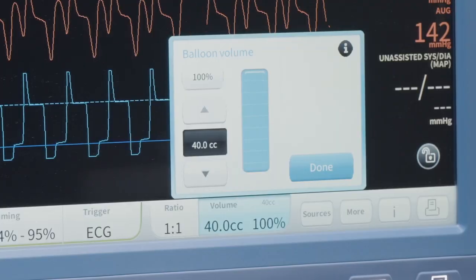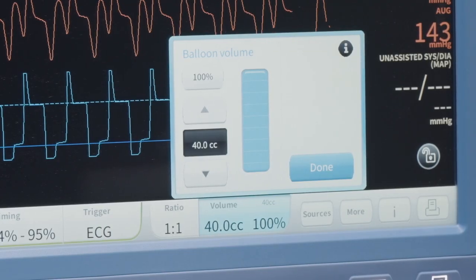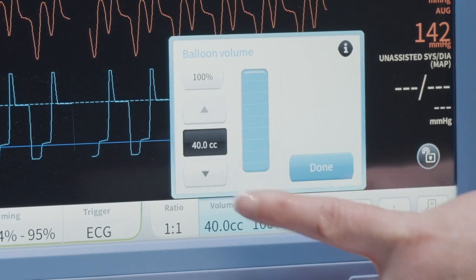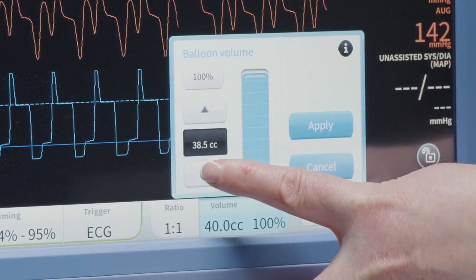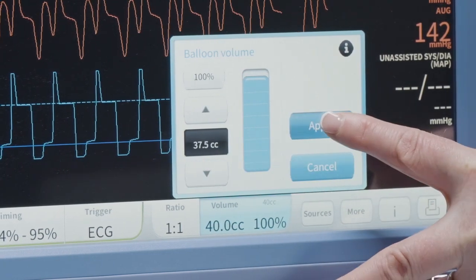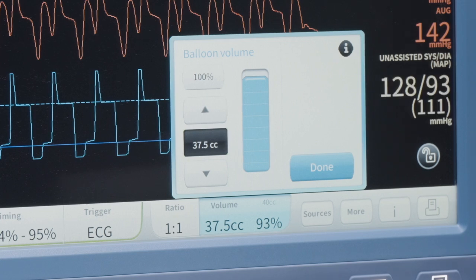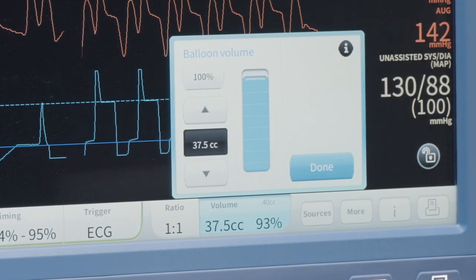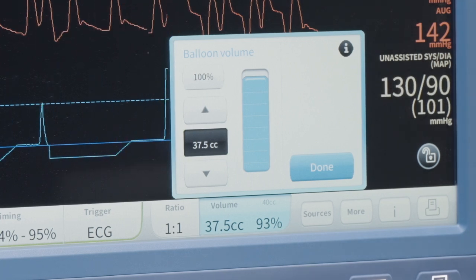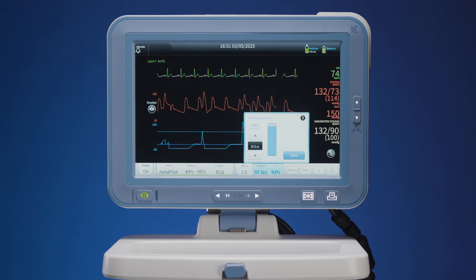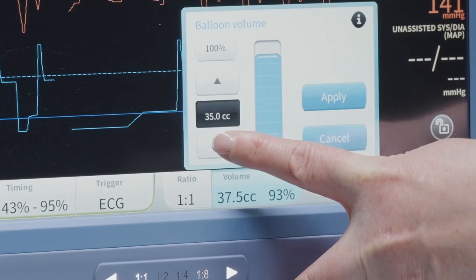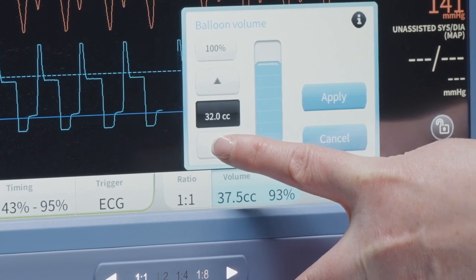The user will increase or decrease the volume to the desired setting. Press Apply to change the volume or cancel if the change is not needed. The pump will reset the volume in 1 to 2 beats and resume pumping. Note, do not reduce the volume delivered to the balloon to less than 2/3 of the capacity of the balloon to decrease the risk of thrombus formation.